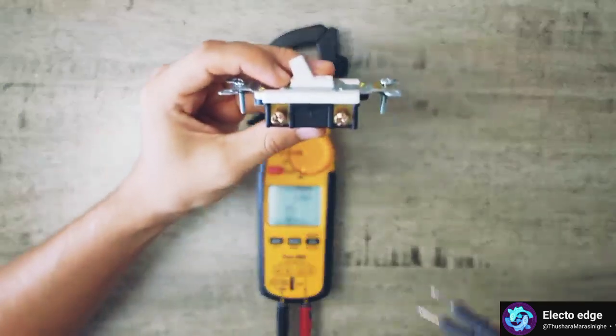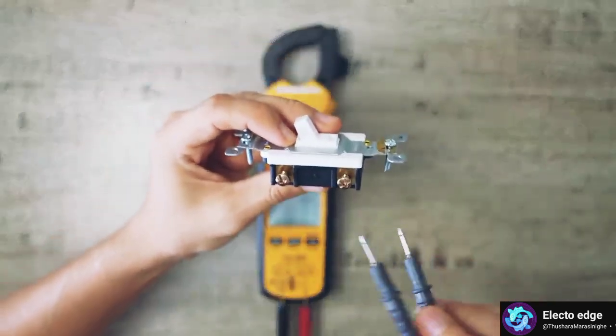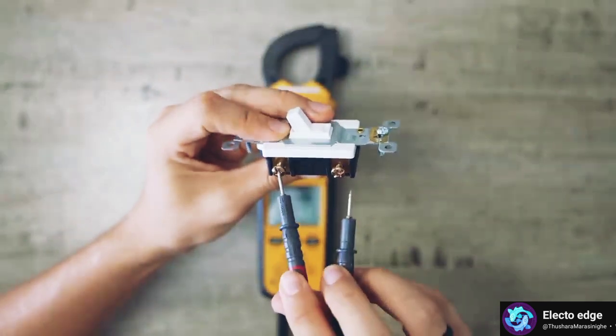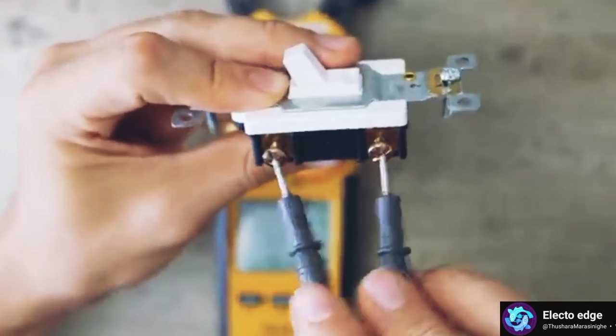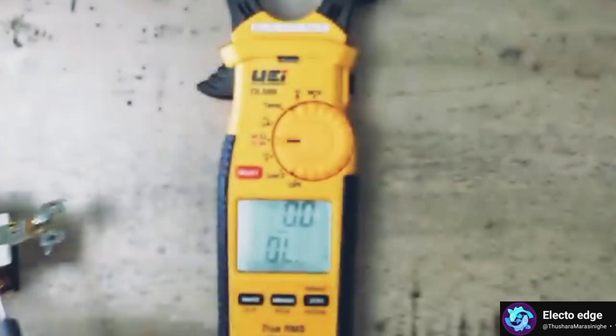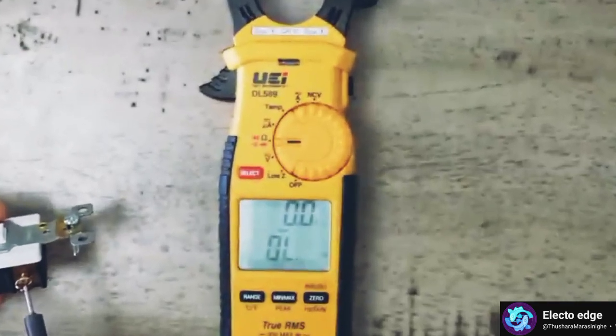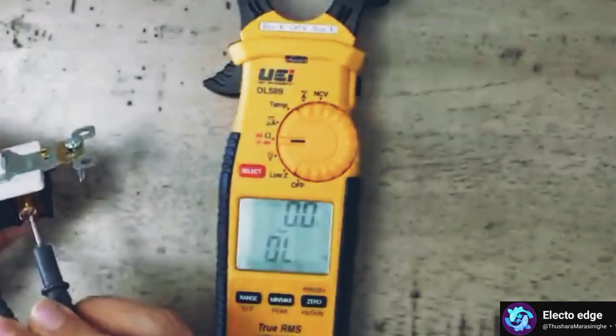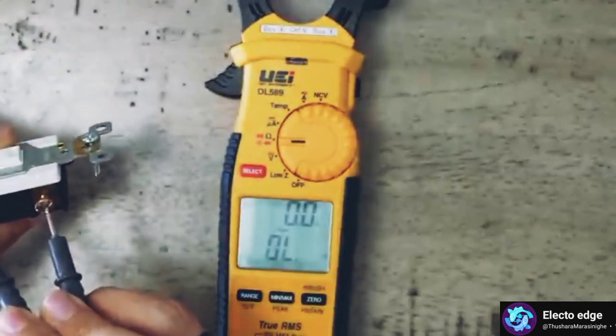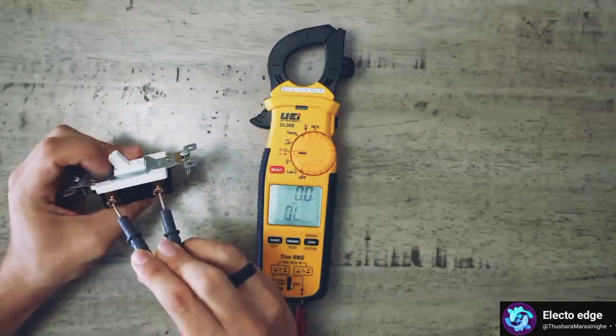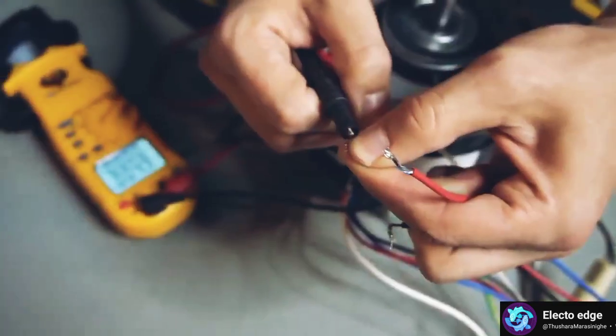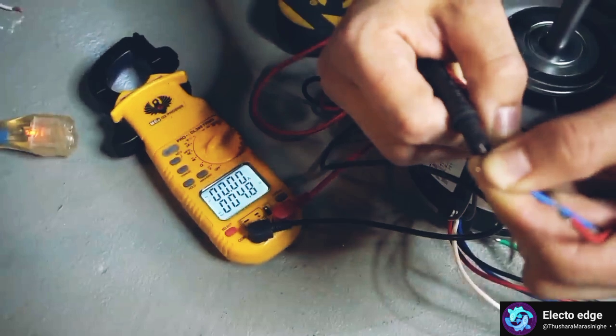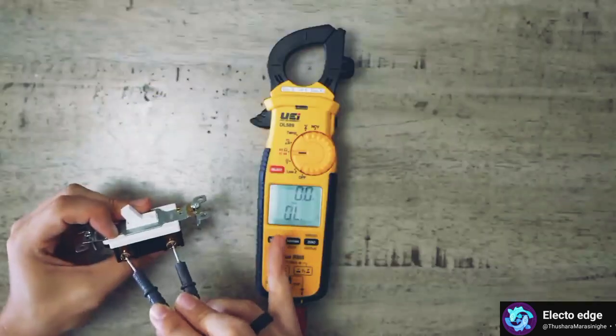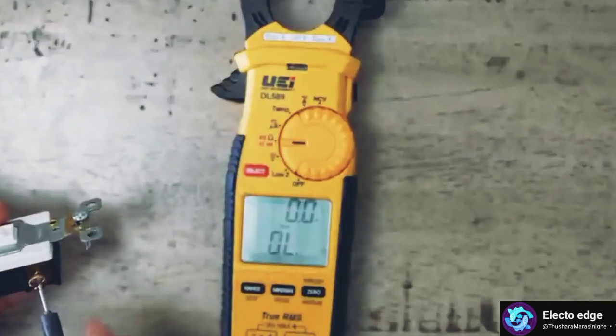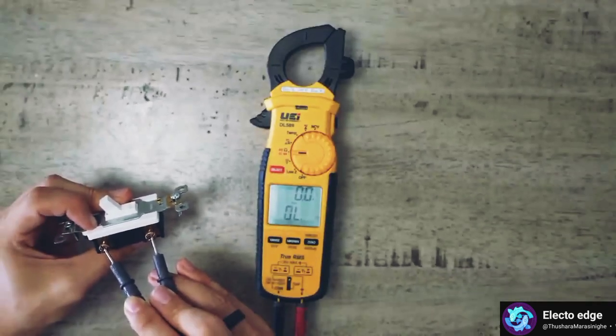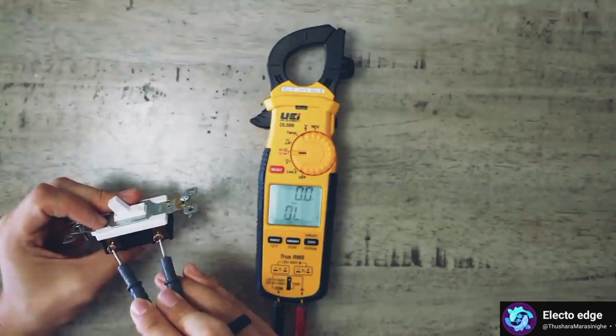So let's try checking the resistance of this light switch. Right now it's in the off position. If I put my meter leads on either end, we see that I'm getting a read of OL. When you see OL, that means that there is no connection between these two points inside of here. So for example, if you were checking a motor winding and you're going to be seeing OL like that, that means that winding inside of that motor is probably burnt out and there's a break inside of that winding.